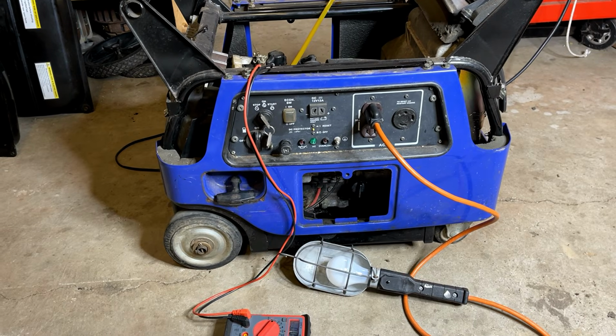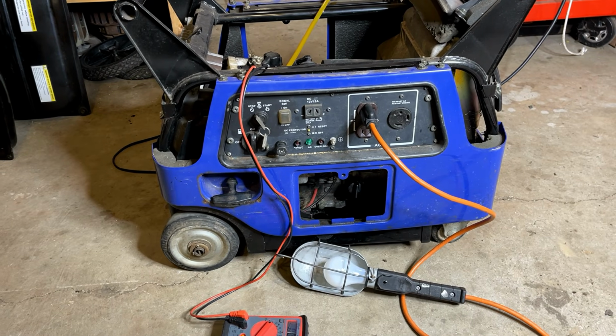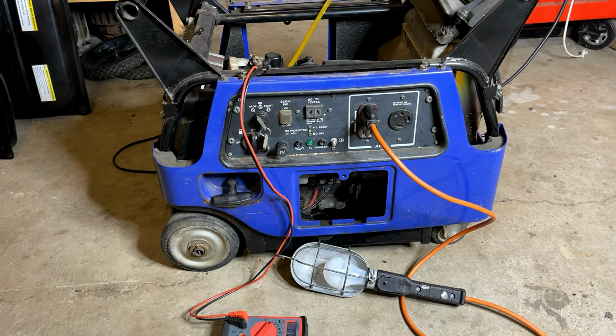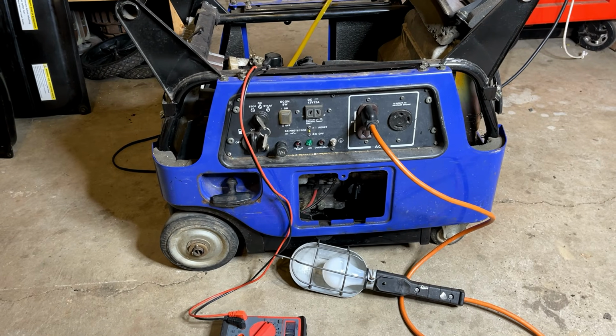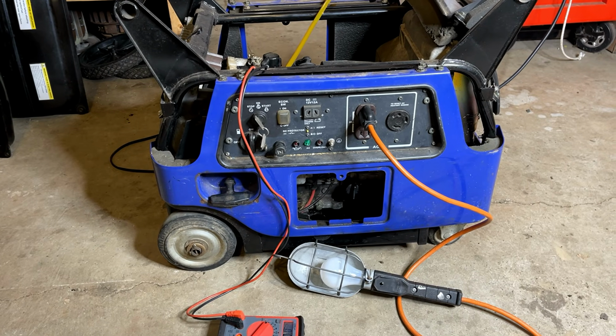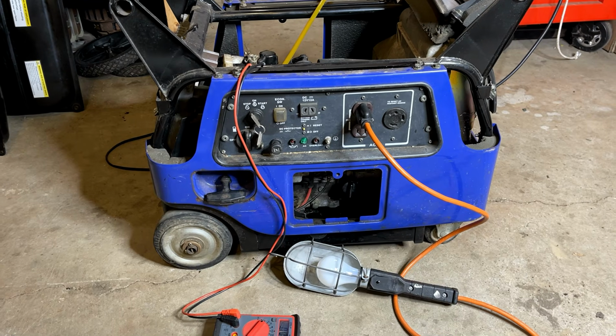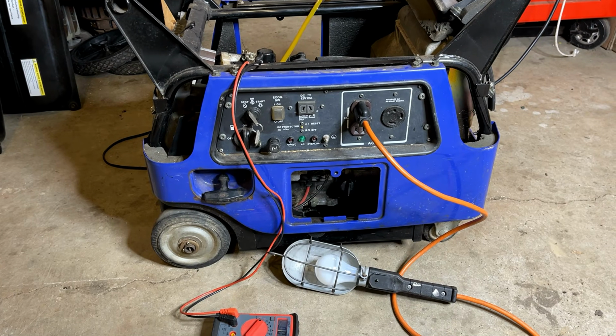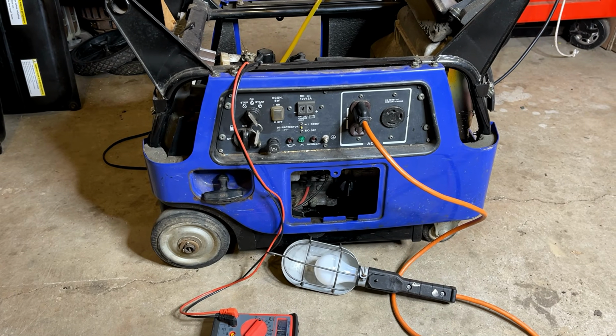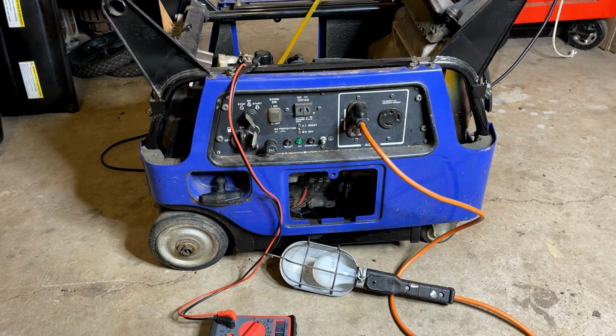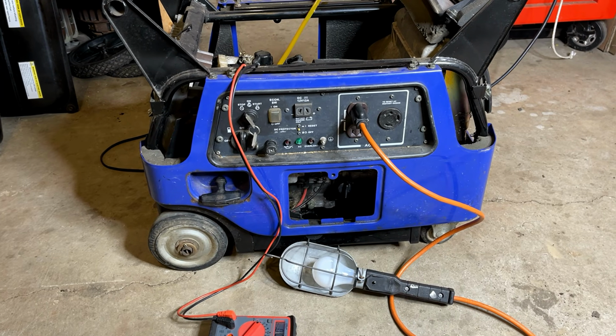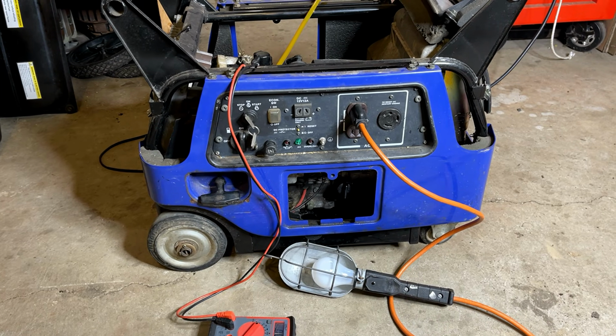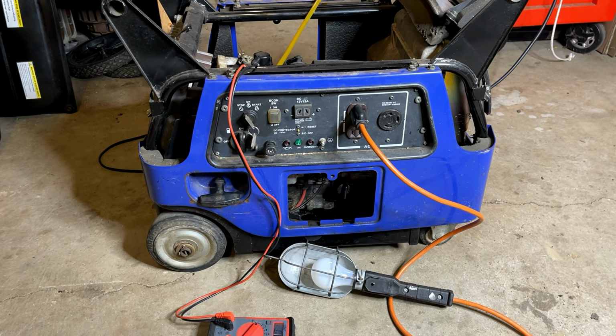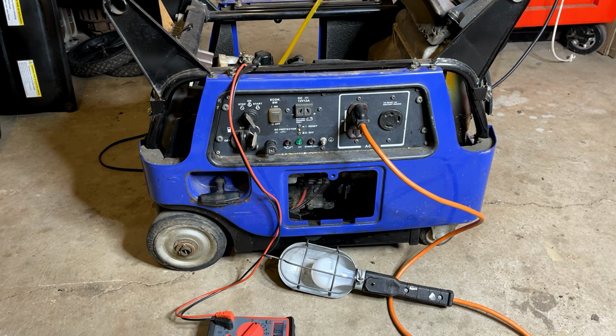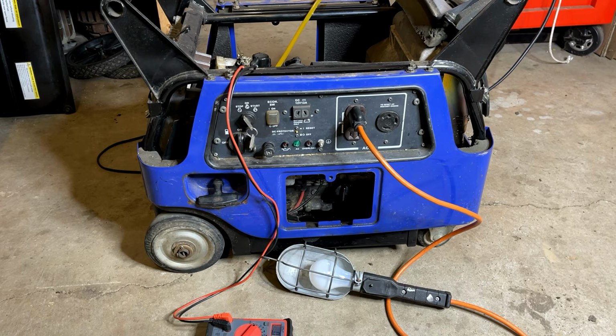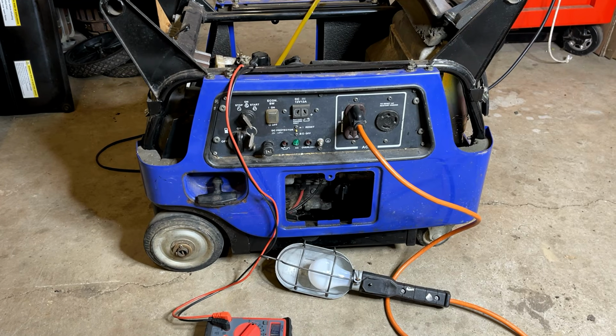Not sure what to think about this one. The output on leg 1 and leg 2 was around 220 volts, but leg 3 is about 100 volts more at 320 volts. And the inverter actually seems to be working when eco throttle is off, which basically increases the voltage across all 3 legs. So potentially it's not an inverter issue. Anyway, I need to do some homework on this, I'm going to look for a service manual and see if that gives me any clues.